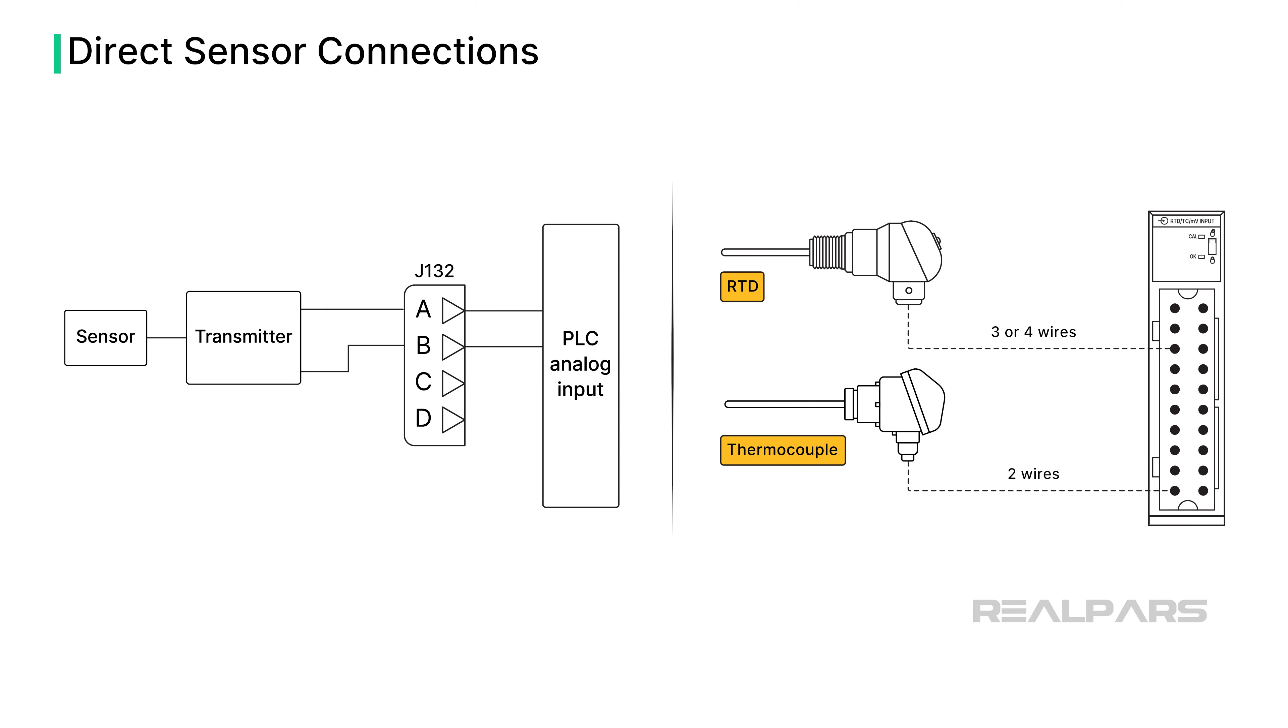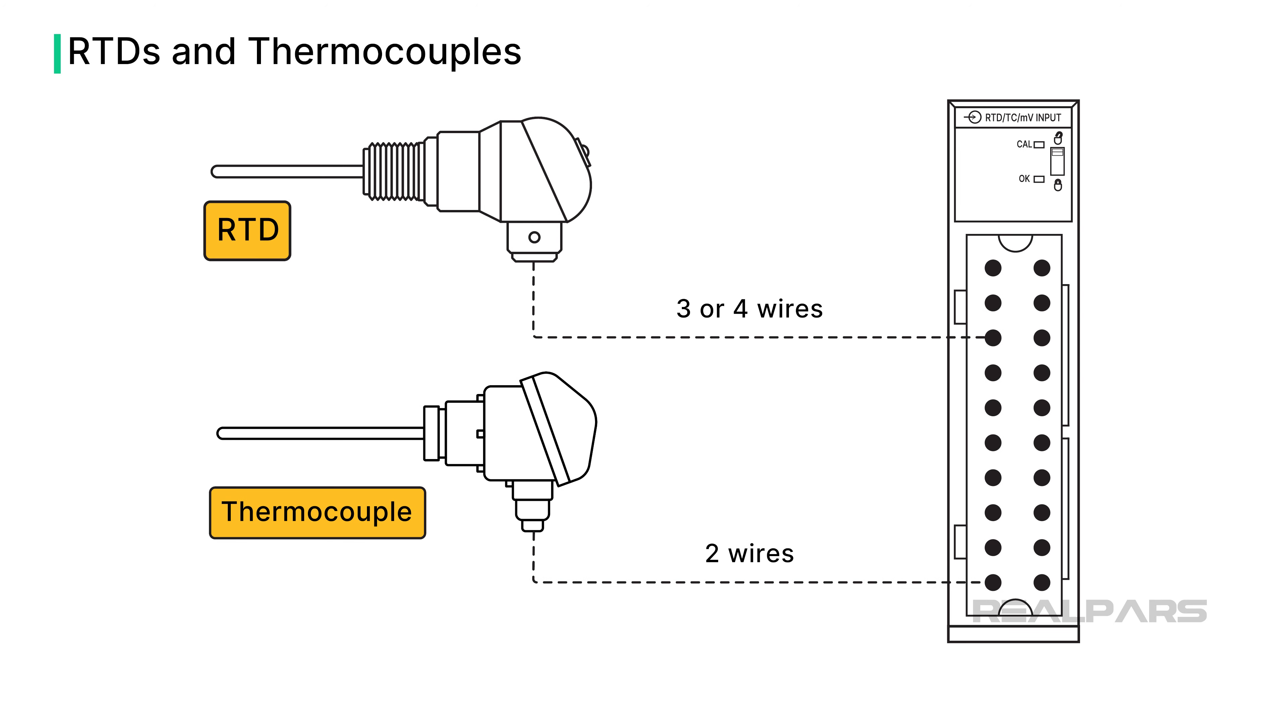As illustrated earlier, temperature sensors can be connected to a transmitter, producing an analog signal of 4 to 20 milliamps, representing a temperature range. RTDs and thermocouples can be directly connected to a PLC analog input module, such as the Allen-Bradley ControlLogix IRT-8i, eliminating the need for a transmitter.